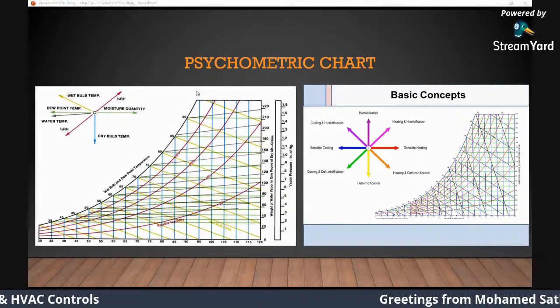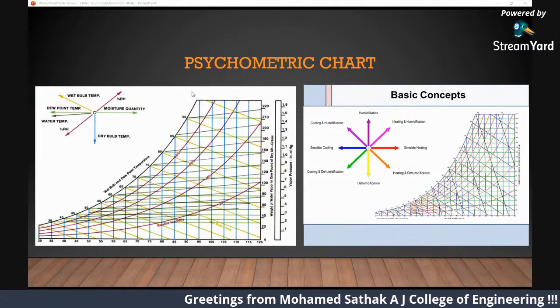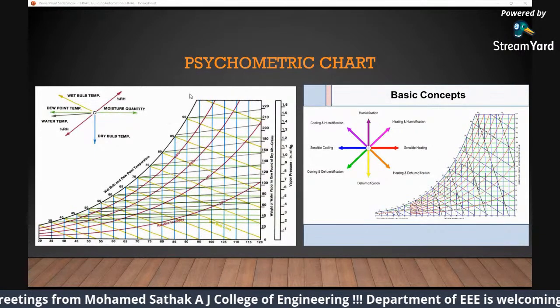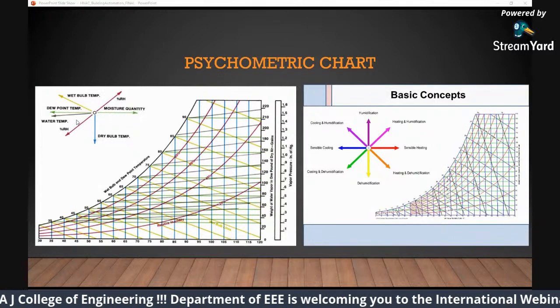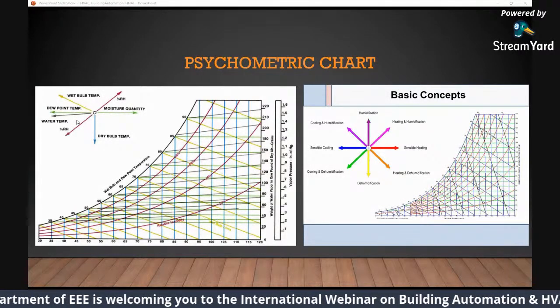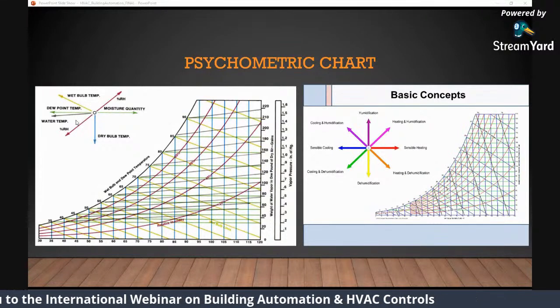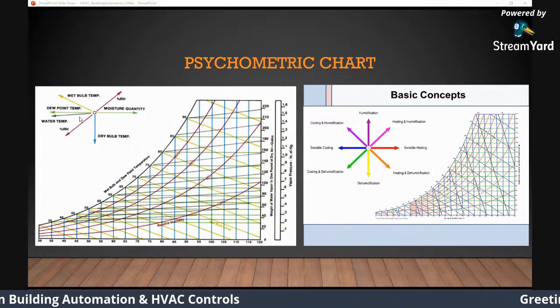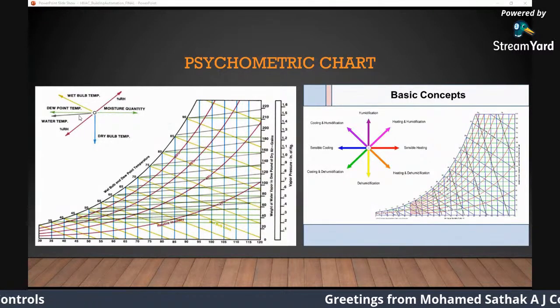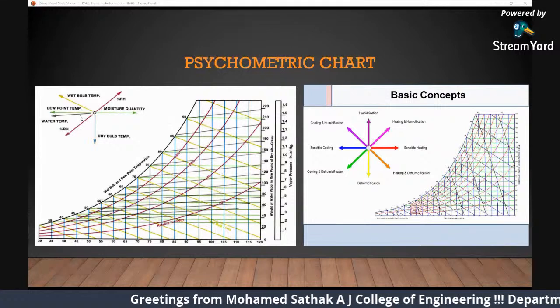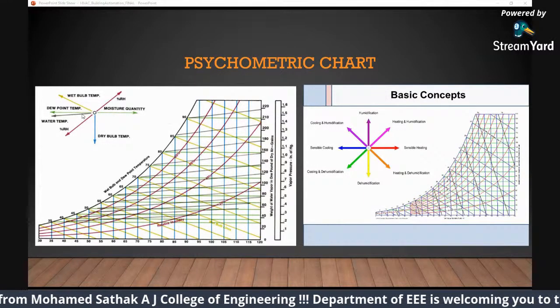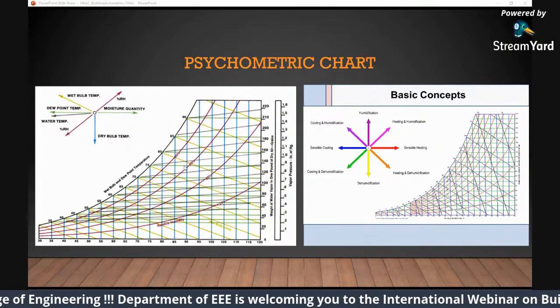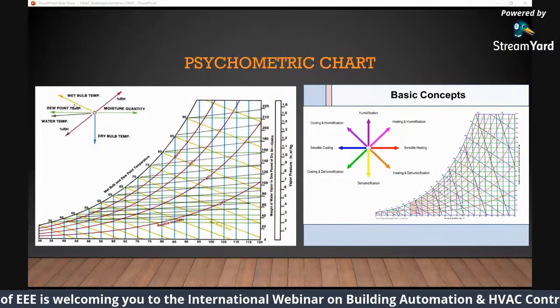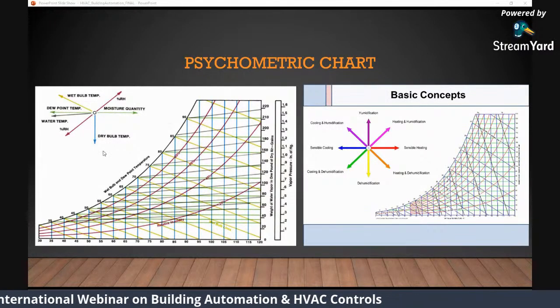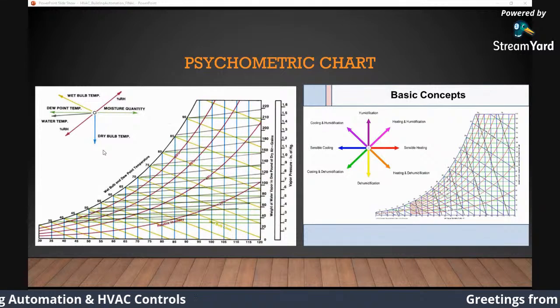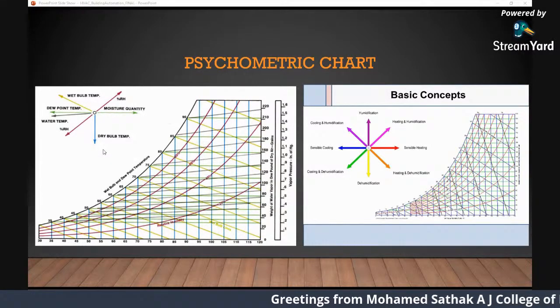Psychrometric chart. I'm not going to get into detail, but I'll tell you this. We are not using psychrometry manually. It's an old concept. Nowadays, we have Android apps to determine your dew point, dry bulb temperature, and everything. These are the technical terms we use in the HVAC field to identify temperatures or humidity factors, sensible heat, latent heat. All this falls under thermodynamic concepts. While designing a cooling tower or designing an AHU, all design engineers will use the psychrometric chart. I just want to let you know that this is one important concept or principle people use in the HVAC field. All right. This is a chart. Let's say there are seven factors. I'm sorry, six factors: wet bulb temperature, dew point, dry bulb, moisture content. If you know three factors, you can identify the others using this chart. It's again an important chart in the HVAC field. Right.